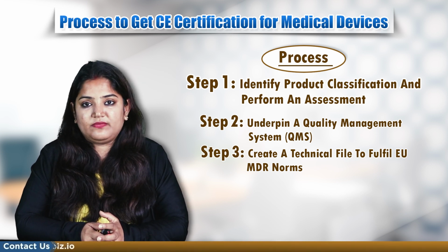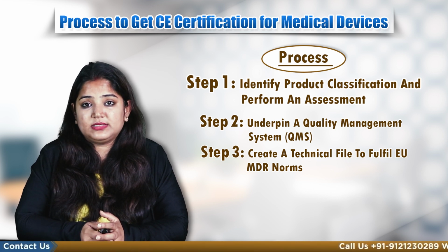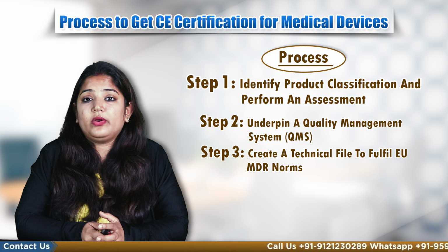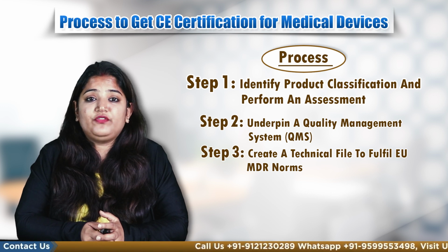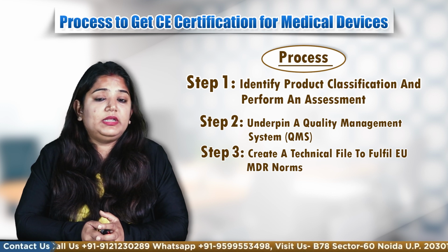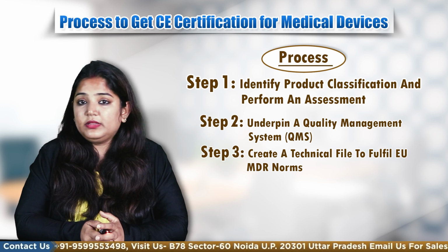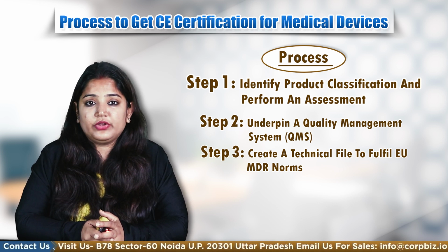certification for medical devices. If your medical device falls under the risk classes 1, 2A or 2B, you have to prepare a technical file that encloses details concerning the device conformity and confirm the adherence to the essential requirements.